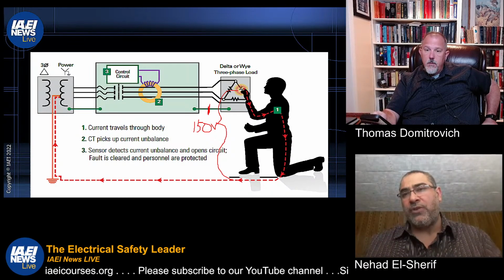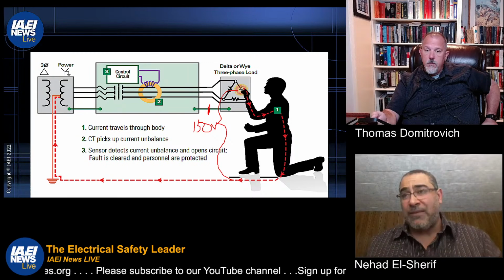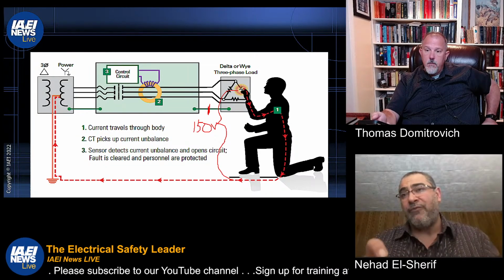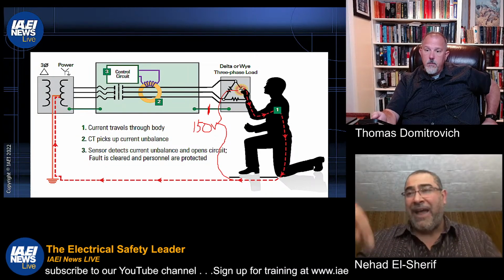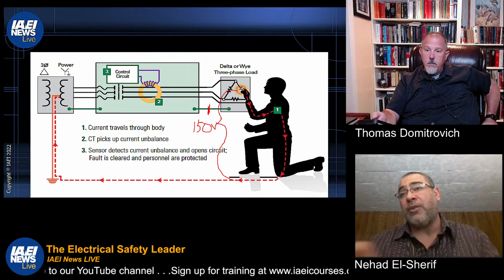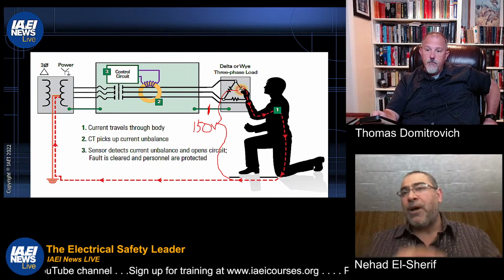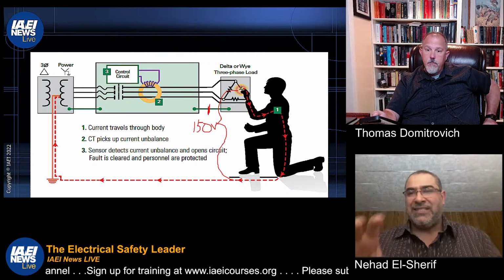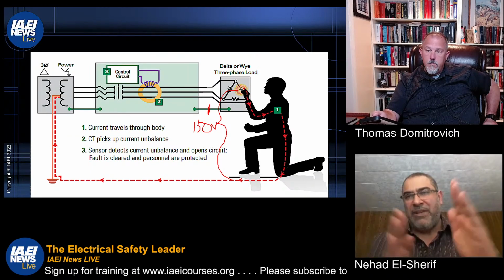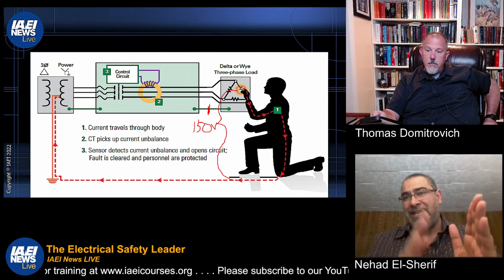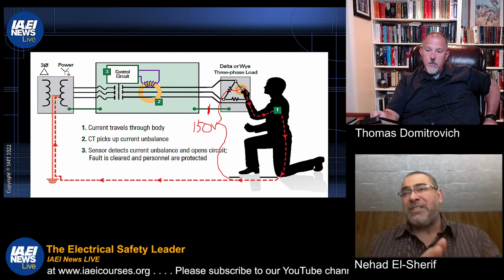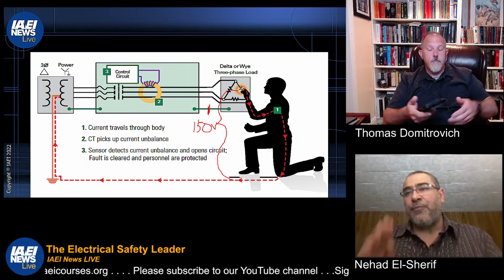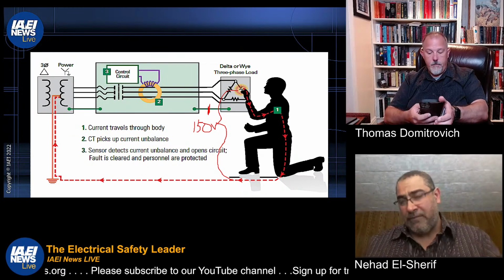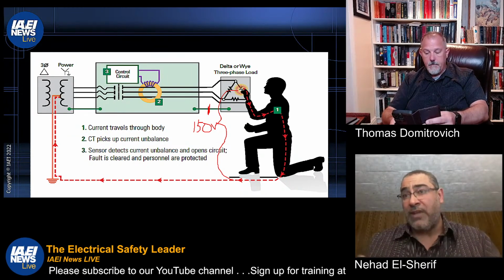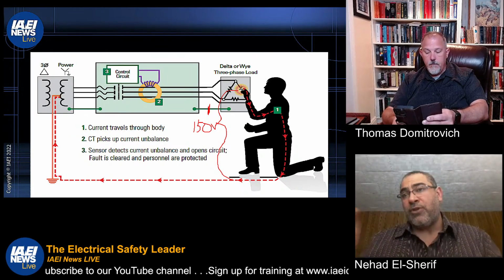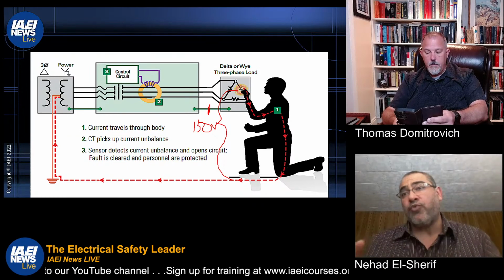So we're trying to make sure that the equipment grounded conductor has less impedance, so that most of the current driven by the 150 volts to ground will actually take the path of the equipment grounded conductor and not the person. Gotcha. Because if there's a problem in the equipment grounded conductor, let's say the impedance of the equipment grounded conductor is exactly the same as the person, then the current will be split in half. Right? If the body impedance is less than the equipment grounded conductor, then more current would go to the person than the equipment grounded conductor, which is not what we want.